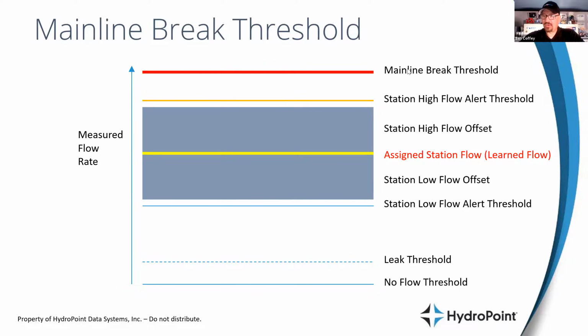We set that mainline break threshold 10 to 20% above the highest anticipated flow. So if I'm only running one station at a time, I look for my biggest station and I set my mainline break threshold to 20% above that, right? So if I run my biggest station at 100 gallons a minute, I set my mainline break threshold to 120 gallons a minute. And normal irrigation shouldn't pass that, right? We shouldn't ever exceed that 120 gallons a minute during normal irrigation. If valves stick, if two stations are running at once or something happens, it could push up past that mainline break threshold. That's the important lesson, is it doesn't always necessarily mean that it's a mainline break. It means that we passed a measured value that passed this mainline break threshold.